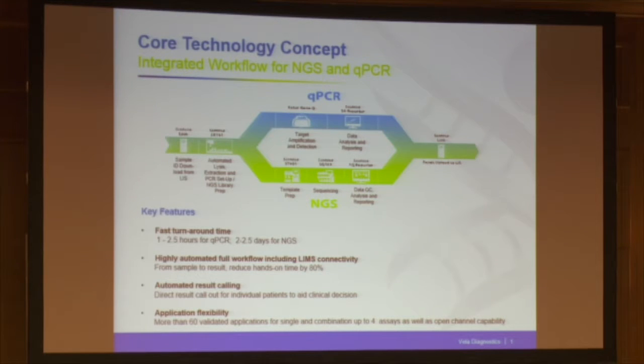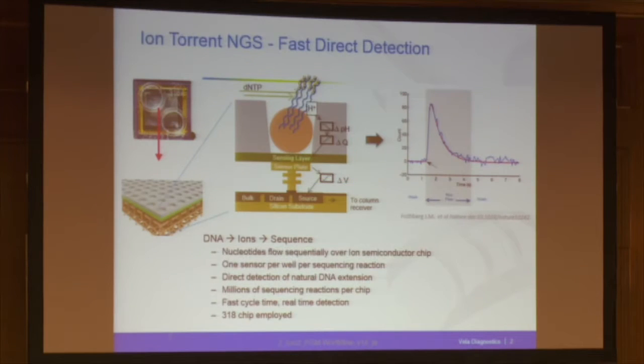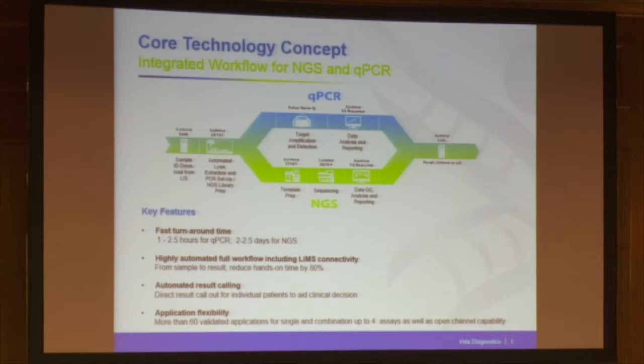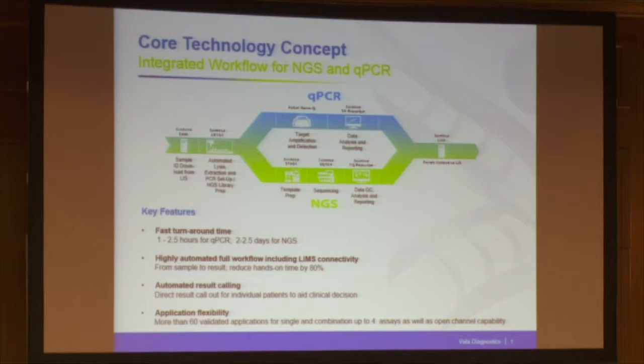As Andreas mentioned, Vela has developed a workflow for NGS that is starting with an automated sample preparation system. With the nucleic acid prepared, the user has the option to either go into PCR or to follow this pathway on next generation sequencing based on ion torrent. In both cases, there is an automated reporting software system proprietary developed by Vela, producing a final report on quality of your runs and also on the clinical data.